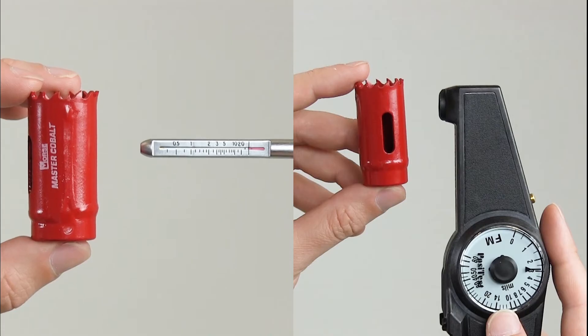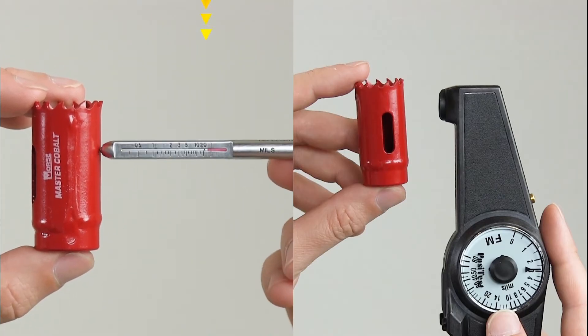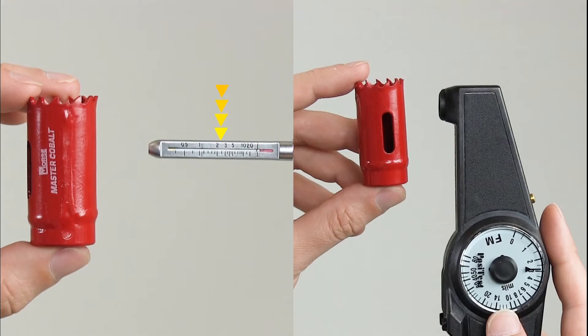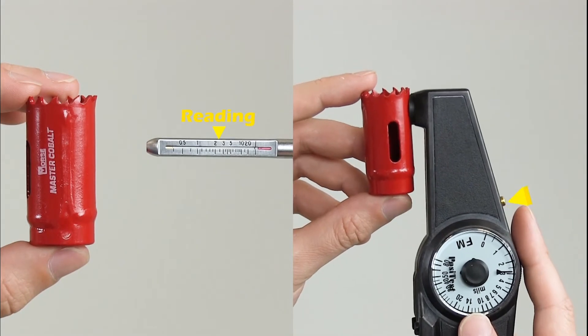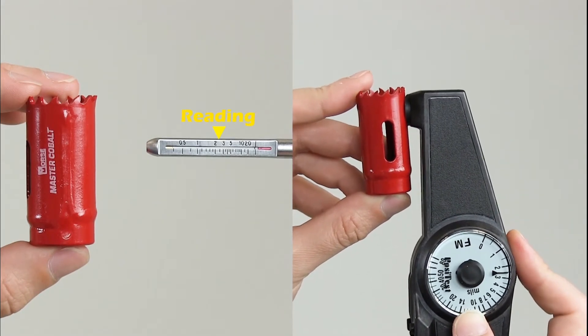Simply place the instrument on the surface and apply force on the spring-loaded magnet until it pulls off. The instrument converts the force required to pull the magnet from the surface into a calibrated thickness reading.